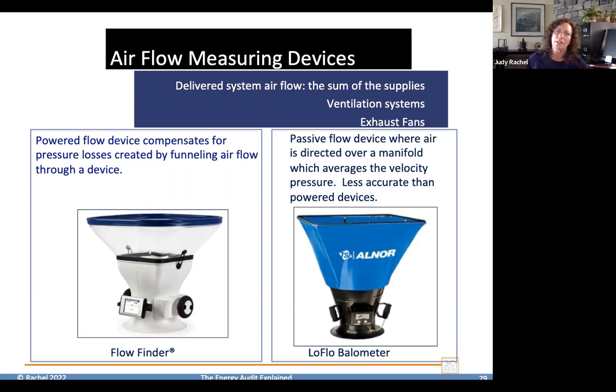And so it's a good entry level piece of equipment so that at least you can measure airflows and be within the ballpark, but it's not particularly accurate, and it does cost probably, I want to say, $1,300 or $1,700. It's up there in price, but the flow finder is over $3,000. It's like $3,500 or $3,800. But they're so important as pieces of equipment that anybody who can make the investment should absolutely be aiming to get a flow finder.